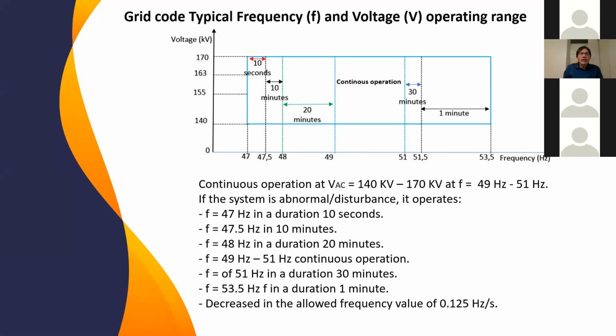Fault ride-through. In order to be compliant with the grid code, the turbine and all apparatus connected offshore should be compliant with the grid code requirement, including fault ride-through. What is the grid code requirement here? This is an example: apparatus, let's say a turbine, operates between 140 kV and 170 kV in continuous and steady state operation, and between 49 Hertz and 51 Hertz. So during continuous operation, this is the rating we have to maintain.